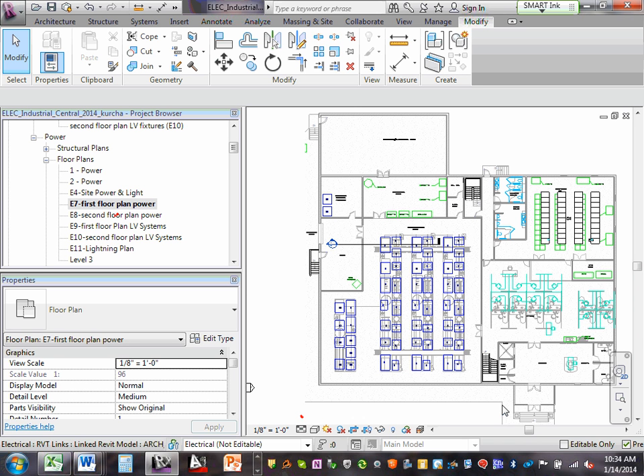Manual pull stations, in the case of this system, would be an addressable device, so we call it a module, not a detector. Detectors relate to the word sensor. You're sensing smoke, heat, gas, whatever the case is. In the case of a manual pull station, we take one of our modules and put it inside a box that's got a handle on it. When we pull that handle down, it closes the contact and turns in an alarm.